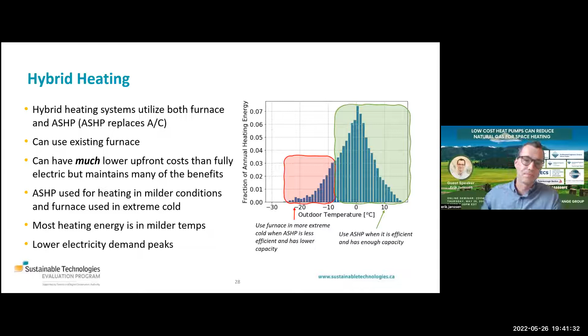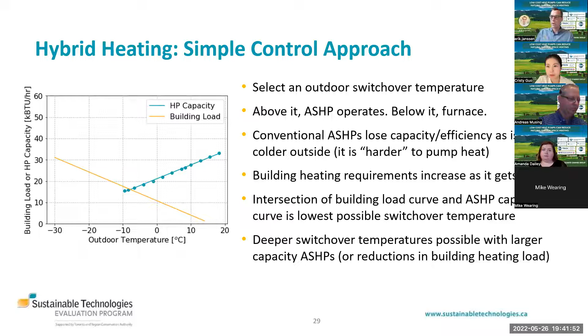There's different approaches to controlling a hybrid heating system. We're going to discuss two. The first doesn't have an official name, but I'm just going to call it the simple control approach. Effectively, you select an outdoor temperature. Above that outdoor temperature, the air source heat pump operates, and below it, the furnace operates, and they never operate at the same time.